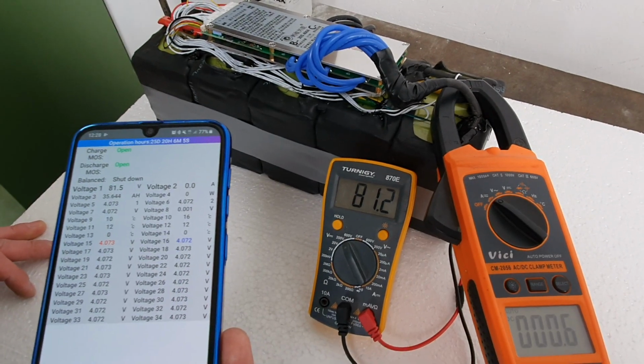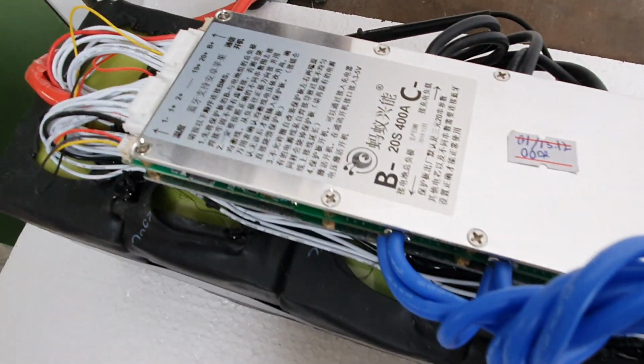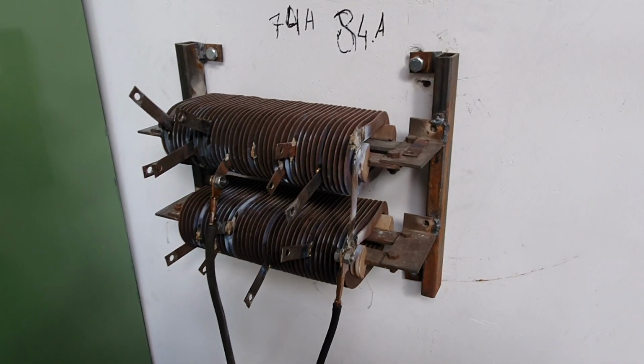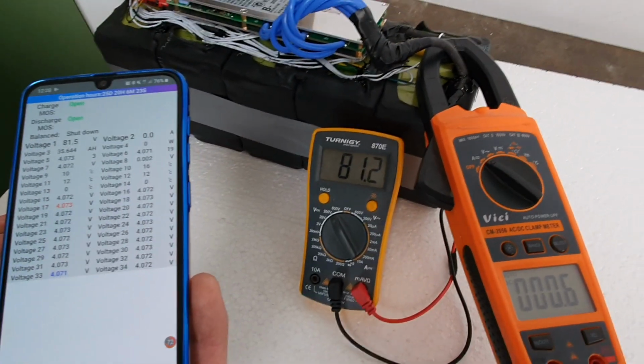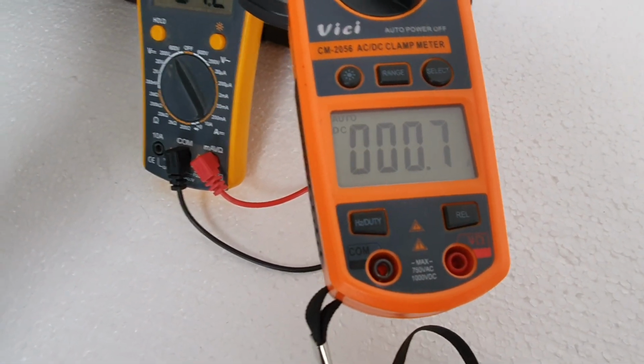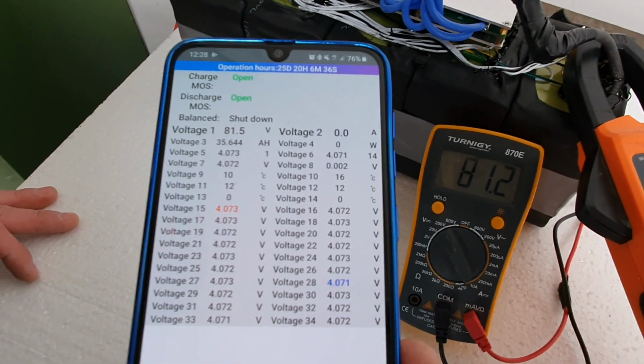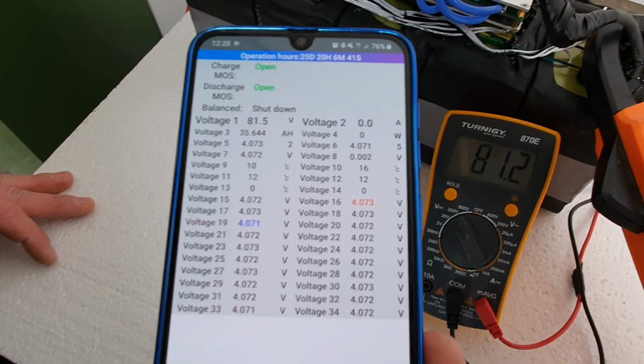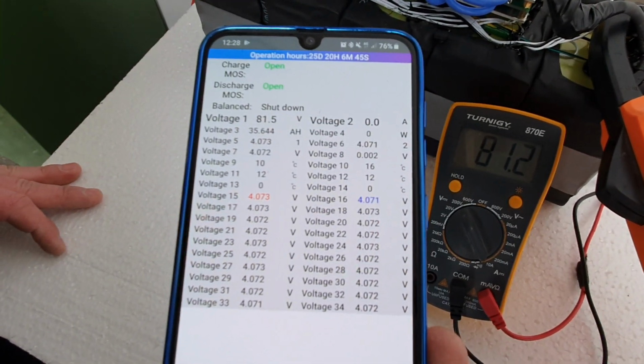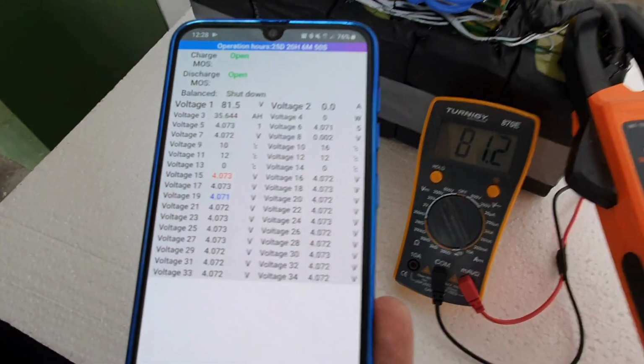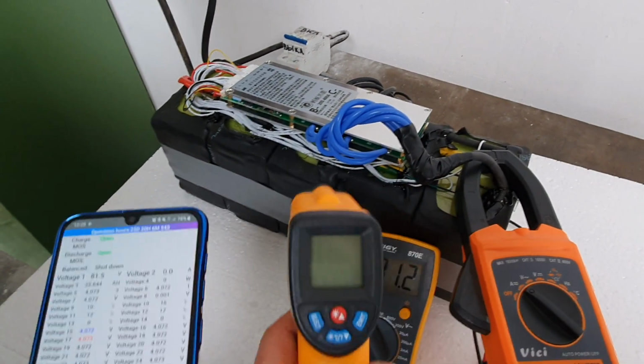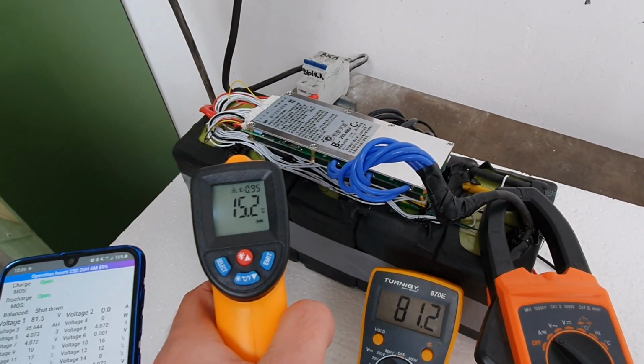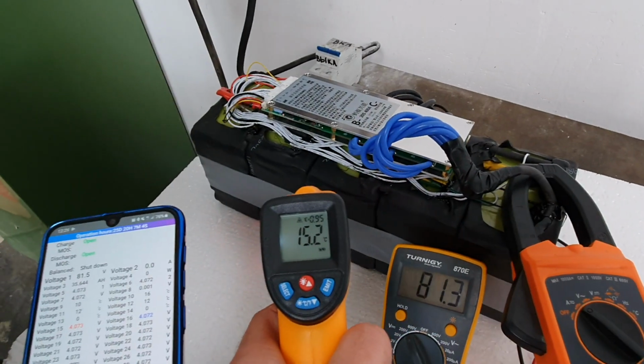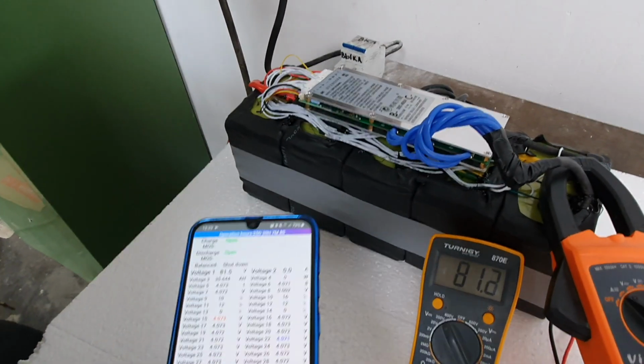We will show the power output of the battery connected to the ANT BMS, and the discharge stand will be this spiral that gets hot while discharging the battery. We have an amp meter and a voltmeter showing total voltage of the battery, as well as the BMS connected to the phone, which shows the voltage of each cell, total amperage, power, and other parameters, as well as the temperature. Plus we have a laser thermometer. Right now it's 15 degrees, and we'll see how the temperature changes during the test.